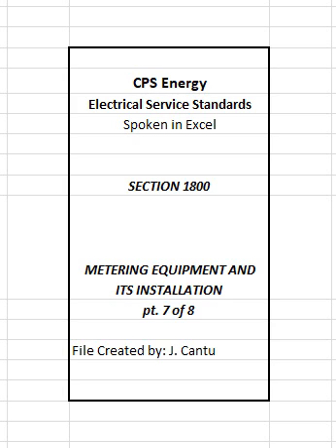1808 6 Grouping meters at cell tower site service installations. Auxiliary gutters used for cell tower site services shall be installed in accordance with Section 1900, see option 1 or 2 below. 1. Service may be designed with a minimum 600 ampere rated main service disconnect on the line side of an auxiliary wire gutter containing a maximum of 2 to 350 kcmil conductors per phase.